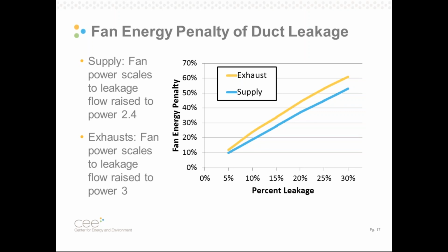So for supply systems, this tends to be an exponent of about 2.4, and for exhaust systems an exponent of 3. But just to give you an example, if you have 10% duct leakage, you're going to see roughly a 15 to 20% increase in fan power. And that's at a moderate amount of duct leakage. Once you get into high rates of duct leakage, like 20 to 25%, you see upwards of a 50% increase in fan power.